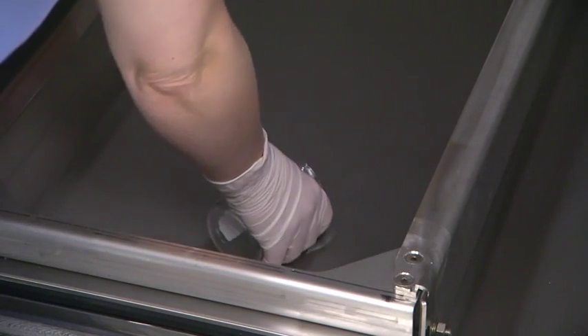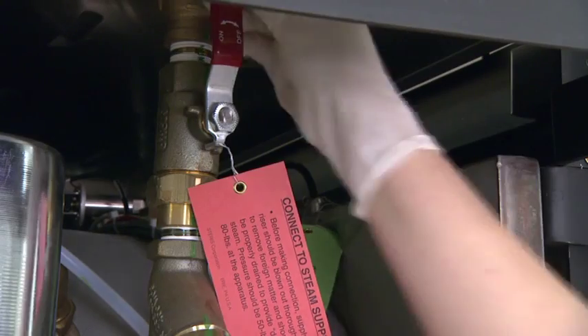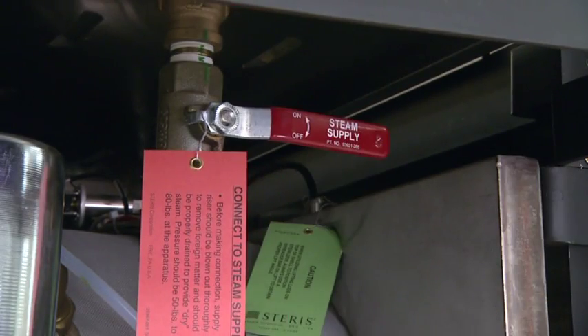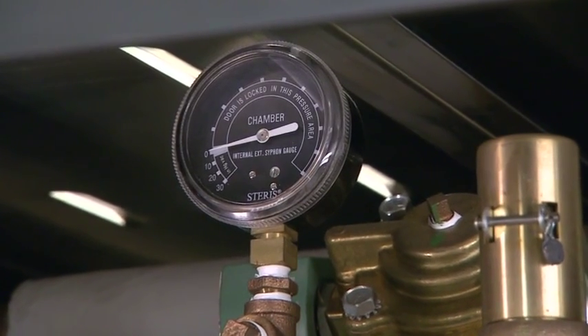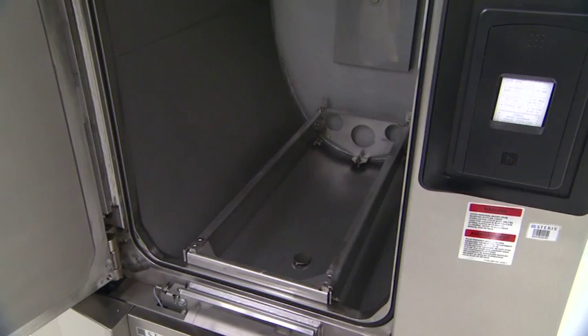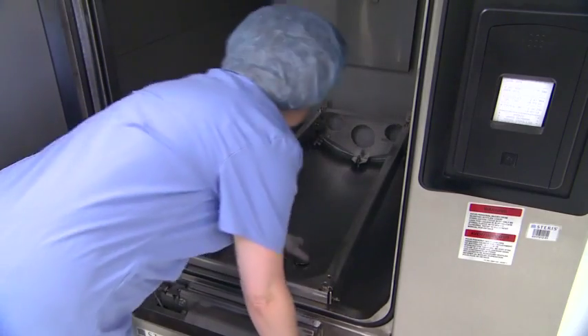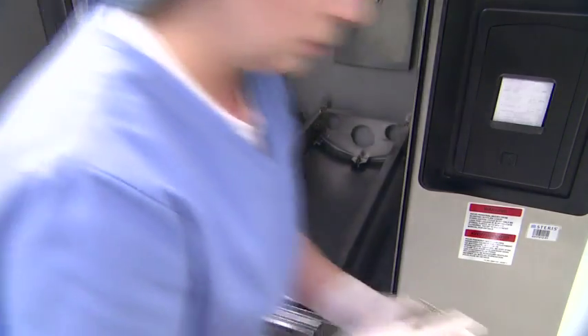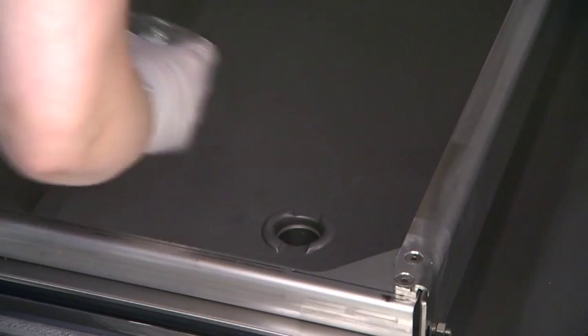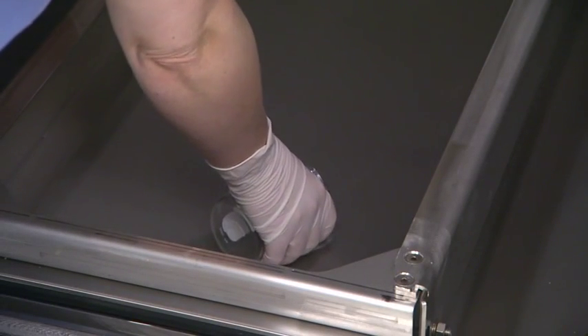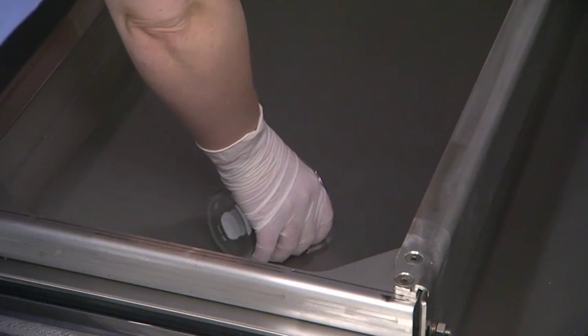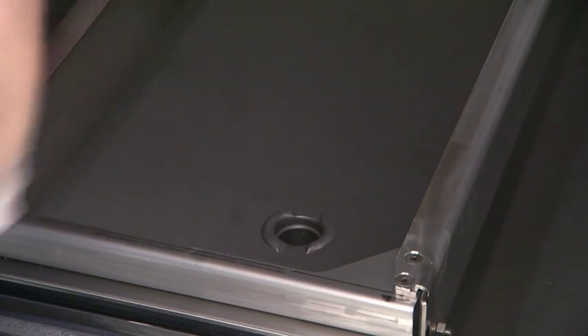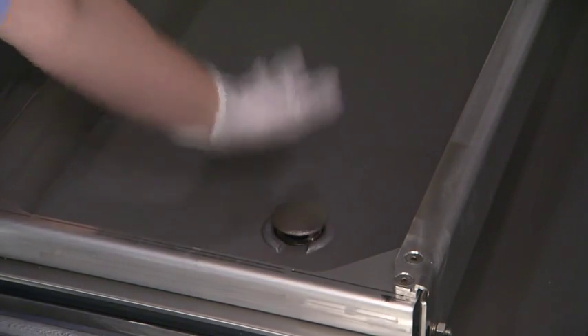Whenever the line becomes clogged, flush the chamber drain. To do this, you turn off the steam supply valve. Wait until the jacket pressure is 0, and wait until the chamber has cooled to room temperature. Remove the chamber drain strainer and clean if necessary. Pour a solution of 1/4 cup of instrument detergent and 1 pint of hot water into the drain, and place the strainer back in the drain.